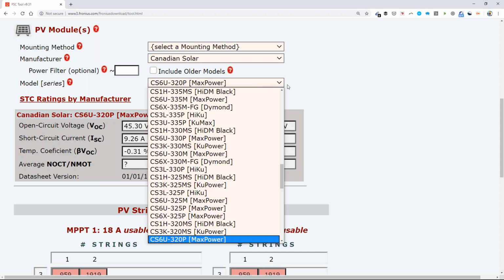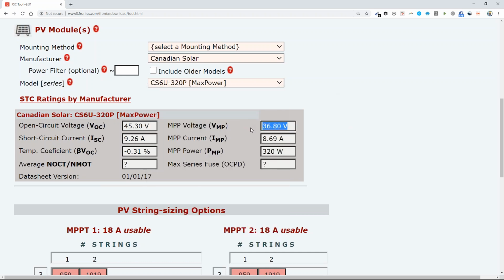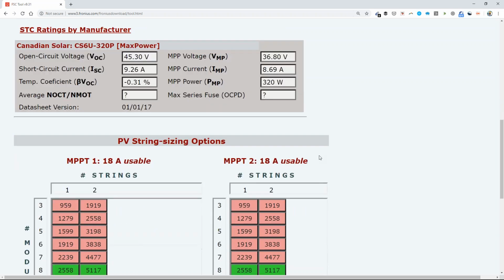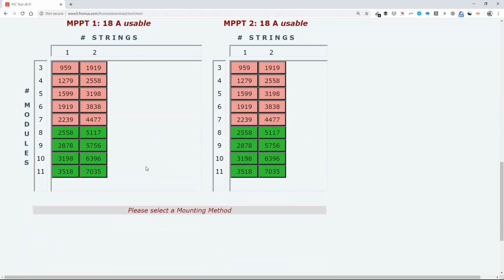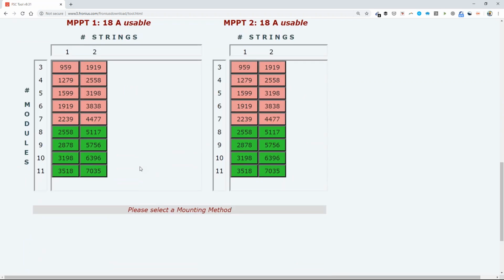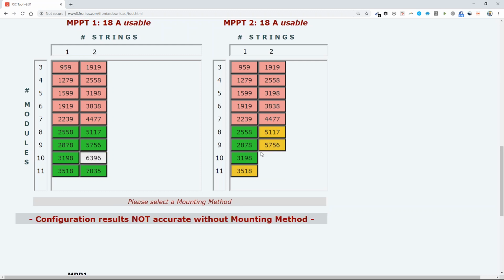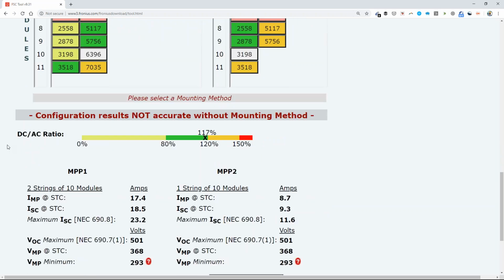If I picked a 72 cell panel, the additional cells means it's going to have a higher voltage and we're not going to fit as many panels on a circuit, but that's okay. Anyway, we get to our input ranges, and remember, we're doing a 30 panel pallet. We have to determine, of these 30 panels, how many are on circuit A and how many are on circuit B. What we could do is 2 strings of 10 and 1 string of 10.